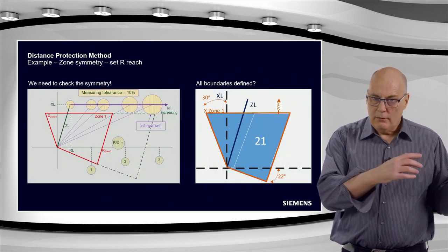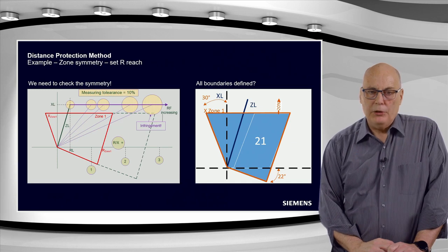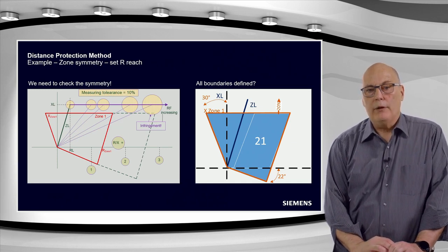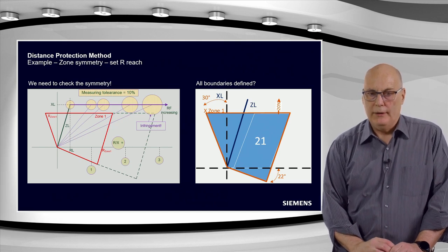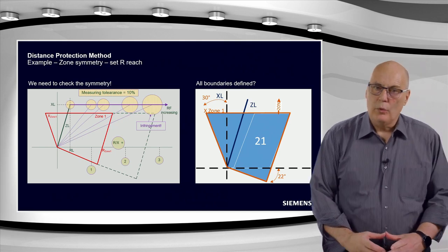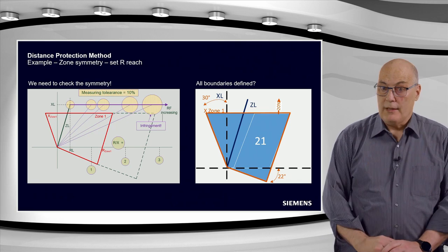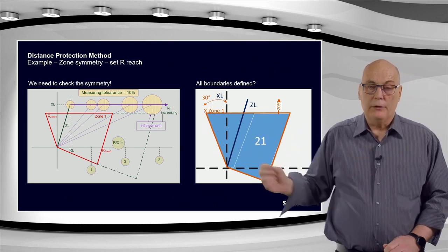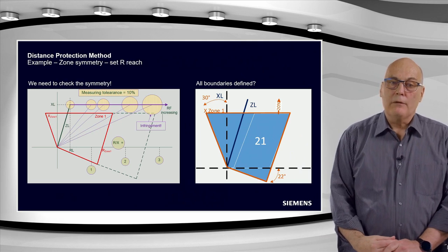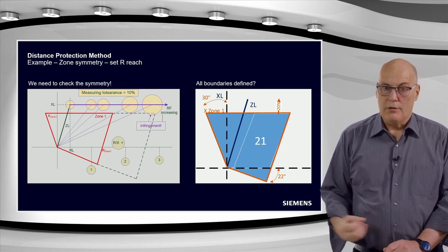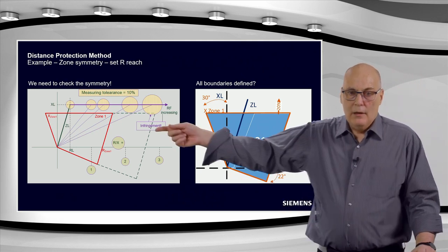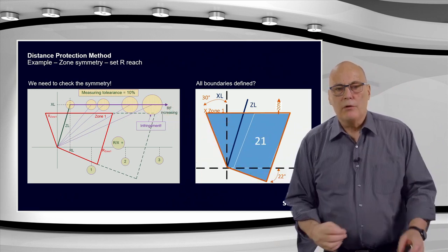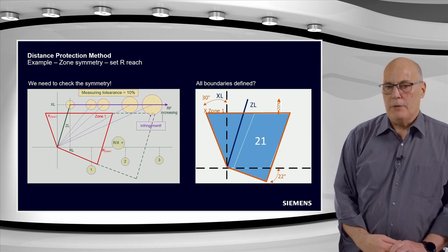But as I think I mentioned in the first session, we now cannot just move on. We have to now, before we finalize this, check the symmetry. And the symmetry condition has to do with the measuring tolerance that I mentioned, that because we have got tolerances, the 20% safety margin must consider that and must obviously be larger than our tolerance. So I just made an example and say that the 20% safety margin we apply was used to take into consideration a real tolerance of 10%.